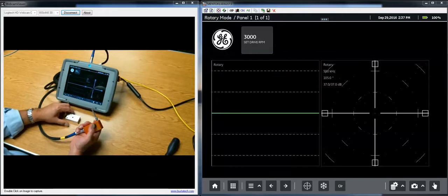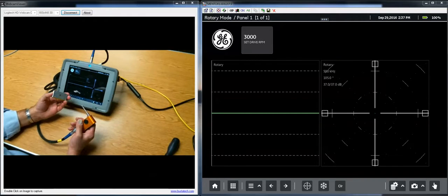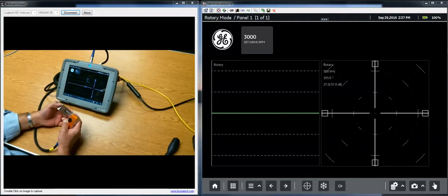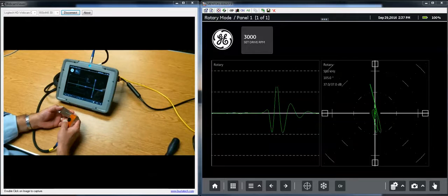If I do a balance, now if I take my probe and start it into the hole in the block, there the probe is just starting to detect the corner notch at the very edge of the hole. Okay. If I go a little bit deeper in, there is the side drilled hole.